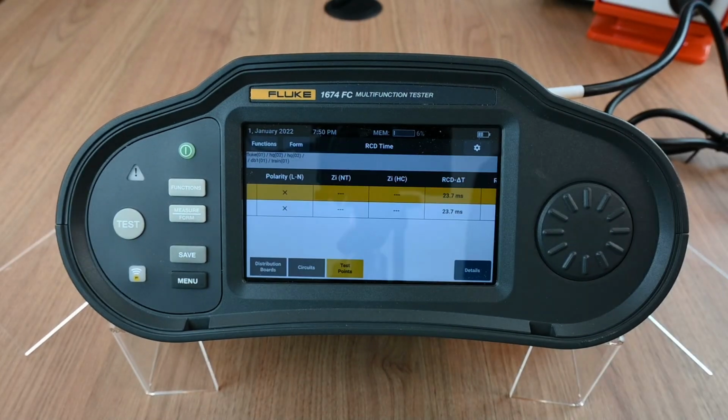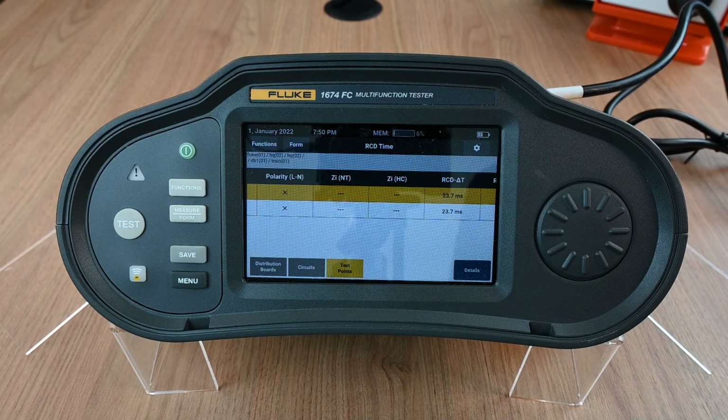I mentioned earlier that the unit has to go into a correct allocation. If that doesn't occur, whether you haven't defined the correct allocation, whether you haven't defined a test, or you're trying to overwrite a test, the unit will do a sequence of things. It will recognize that the test is not valid for where you want to measure it. It will then clear the memory. That's a very deliberate step. It'll clear the memory and then ask you to restart the test. Depending upon the severity of that clearing of memory, it may actually go blank momentarily and then come back.